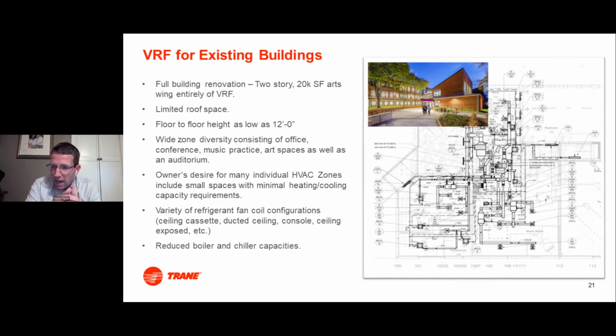And then the owners desired a lot of individual temperature controls for all these small and large spaces. We thought it was tailor-made for VRF. And the VRF system gave us a lot of flexibility because we only had to mount, I think it was at the end of the day, 3 or 4 condensing units on the roof and have that much roof space to use. Also, because there wasn't much ceiling space, it allowed us the flexibility of indoor fan coil units. Anything from ceiling cassette units to ducted ceiling units, console units, and even some other units just exposed underneath the ceiling. And one huge benefit to this too was just by taking this 20,000 square foot building, it allowed us to reduce our central boiler and chiller sizes. So for a lot of reasons like this, it was just a perfect system to use.